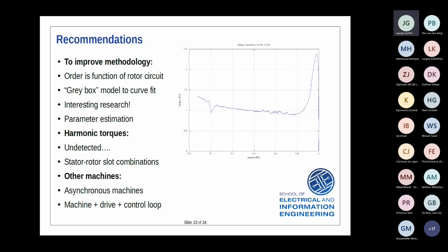One of the weaknesses of this technique is harmonic torques. Here's a machine with a very nice classic curve but a very evident harmonic torque, obviously due to the stator rotor slot combinations. This was a problematic machine to test, because with the locked rotor torque, it was hard to differentiate whether the harmonic torque was to the left of zero speed, to the right of zero speed, or at zero speed. So where do you put the locked rotor test value? Over here, over there, or over there? This was an interesting machine.